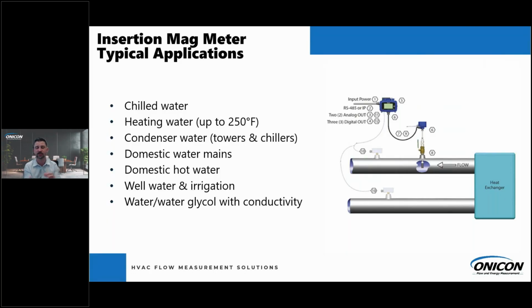But we've seen a shift in the industry where people are asking for no moving parts to remove the maintenance required. So this is great for chilled water, hot water, condenser water, and also domestic water. It is NSF approved. Really any water application with at least 20 microsiemens of conductivity, so it wouldn't be a good solution for something like ultra pure water.